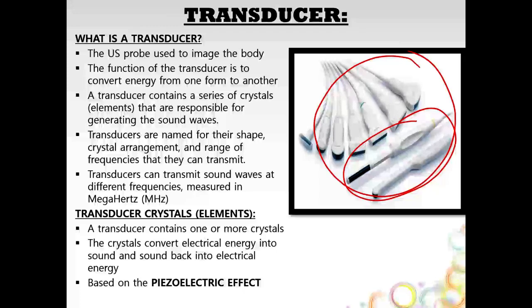Transducers don't need to penetrate as deeply into the body to get through all the breast tissue. And in the breast, we really need to pay attention to resolution. We care deeply about what the picture looks like and being able to distinguish small structures from each other and small differences in the breast tissue. So we care more about resolution than we do penetration in breast imaging. So we will always be using a high frequency transducer for breast imaging.